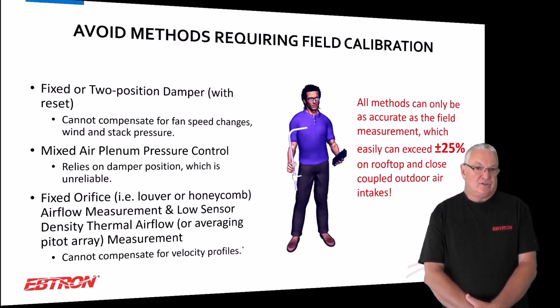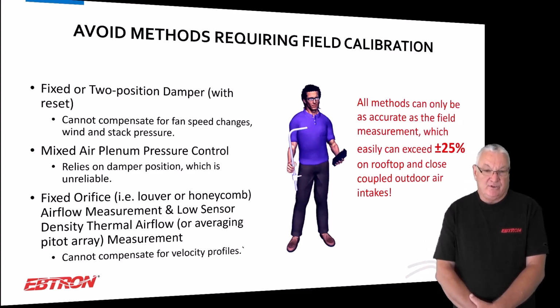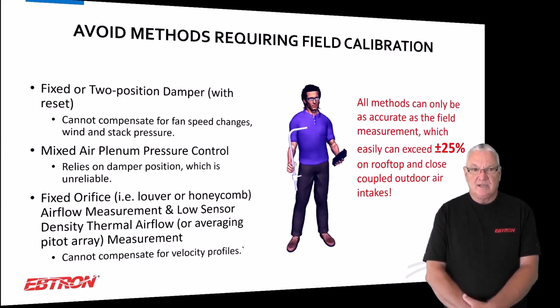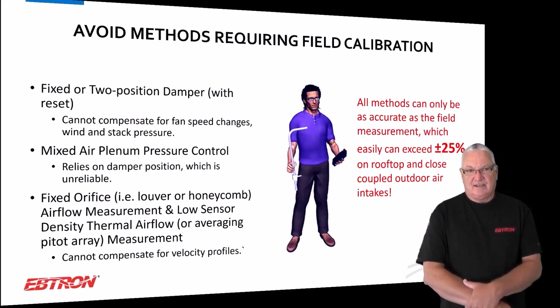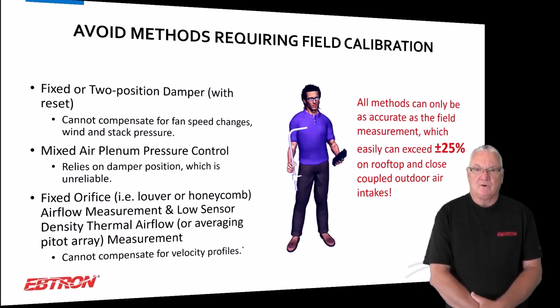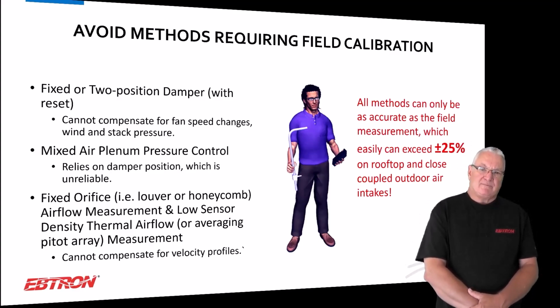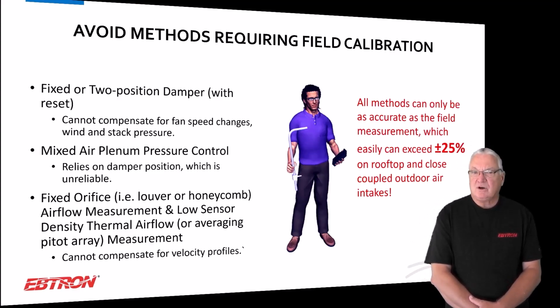And particularly when it's installed, but you wouldn't know it anyhow. Mixed Air Plenum Pressure Control, you need to determine what the flow is. And like I said, we'll just forget the damper position ones because they're terrible. And now I say 25% here. I'm really talking rooftop units.